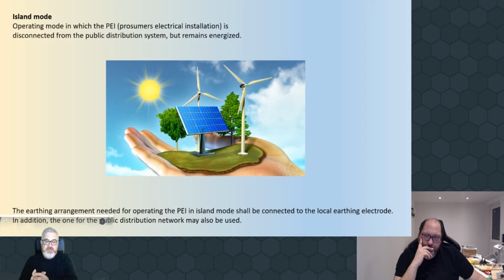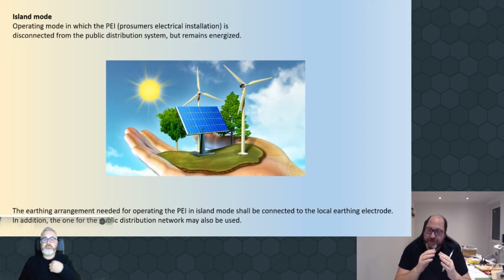It's going to change the rules of the game, isn't it, Dave? It's going to change some of the design requirements as well. I did have a little preview in 60364-8-2, and it starts talking about things like your earth fault currents - you've got to have minimum and maximum, because obviously you've got to make sure that if you're on the DNO earth that you achieve that. But you've also got to make sure if you do disconnect from that supply and you're now an island, so to speak, on your own little network, that you have a sufficient earth fault current there as well. So there's an adjustment to make in those designs, which will be fun to work out.